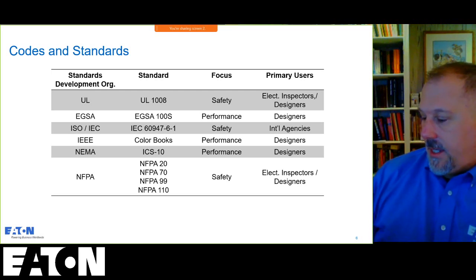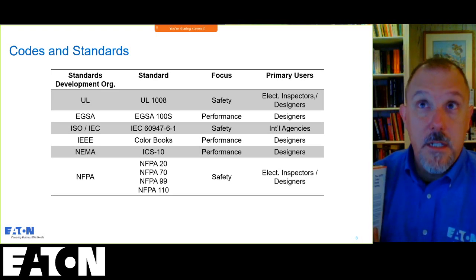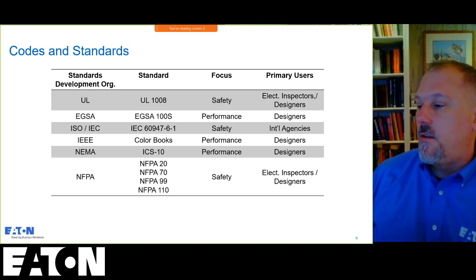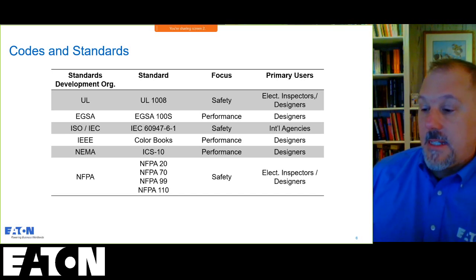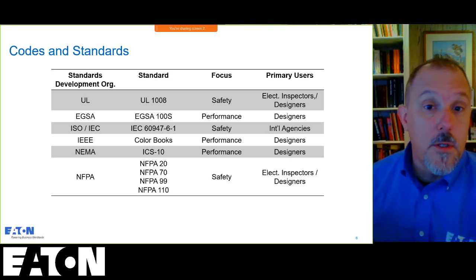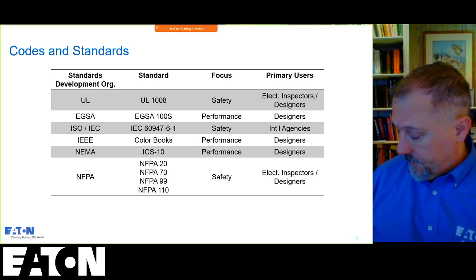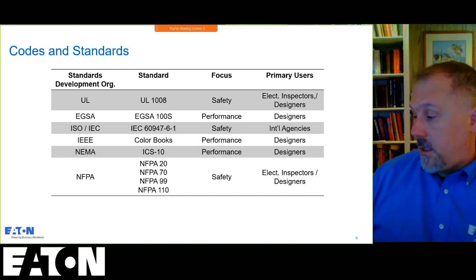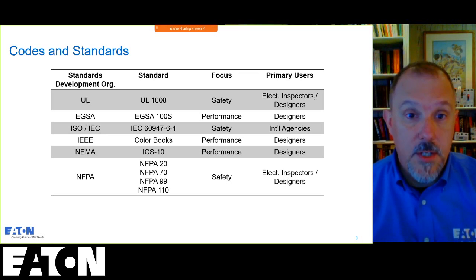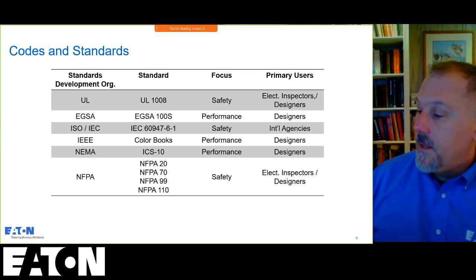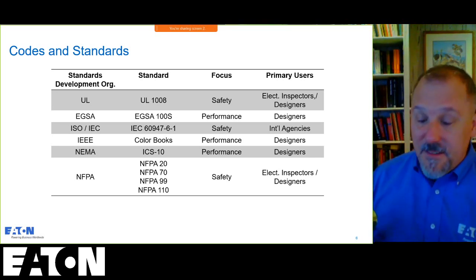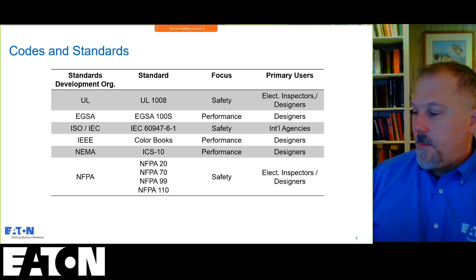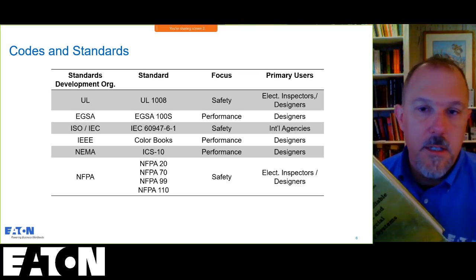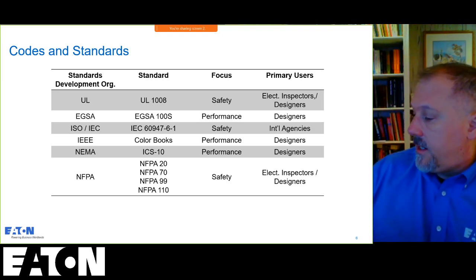But the three books that I would say are directly related to this topic are, first, your IEEE Orange book, which is IEEE Standard 446, titled Emergency and Standby Power Systems for Industrial and Commercial Applications, because we're talking generators. Standby power is appropriate. Then the healthcare white book, IEEE Electric Systems in Healthcare Facilities. I believe hospitals have a lot of local standby generation. That's IEEE Standard 602, and again, this is the 1986 version, but they have newer versions. And then the other one is IEEE Standard 493, the design of reliable industrial and commercial power systems, which is the gold book. Very good.